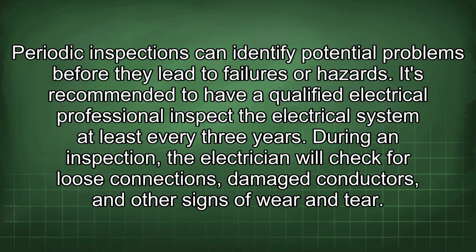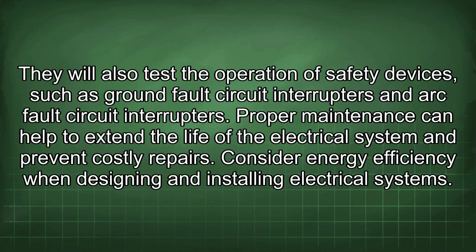During an inspection, the electrician will check for loose connections, damaged conductors, and other signs of wear and tear. They will also test the operation of safety devices, such as ground fault circuit interrupters and arc fault circuit interrupters. Proper maintenance can help to extend the life of the electrical system and prevent costly repairs.